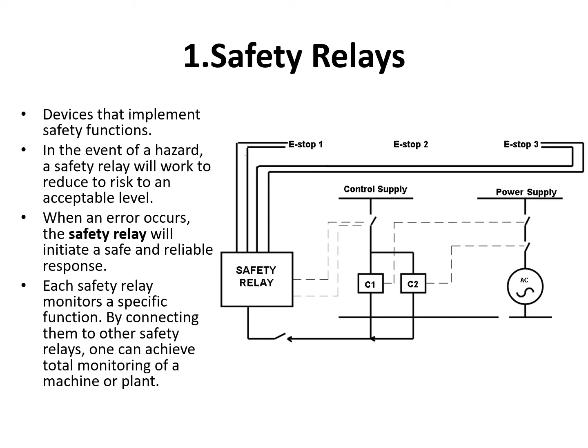Then you can see the safety relay. So when any error occurs, this safety relay will initiate a safe and reliable response. Each safety relay monitors a specific function. By connecting them to other safety relays, one can achieve total monitoring of a plant or machinery. In the above safety relays, all emergency stop buttons are wired in series. The dual contactors are used for redundancy. The reset circuit monitors contactors before allowing the reset to occur.